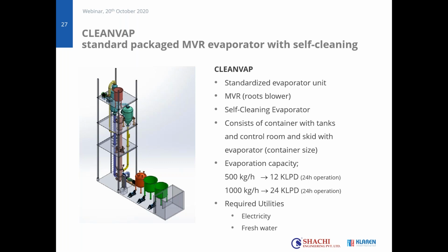Another question which I really like is: till what concentration can we go? Because that's also important to mention. What we sometimes notice is that people focus on the energy use of the MVR units, but later they need a lot more energy to drive the agitated thin film dryer or to go to the spray dryer. In fact, if you can go to higher concentrations, you have less product coming from the evaporator system. It means less effluent that you need to treat in your downstream equipment. So that saves you even more energy. So going to higher concentrations is really beneficial.